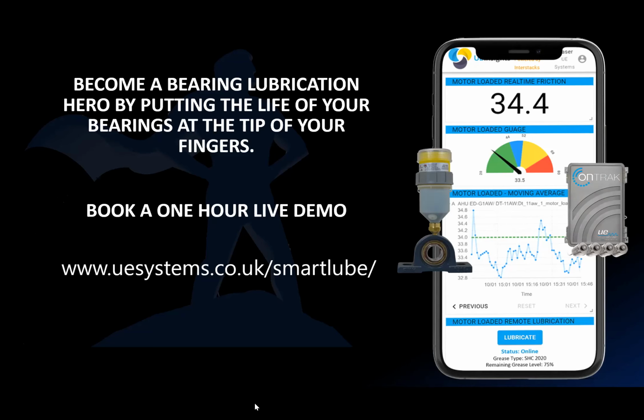Can this system be used to monitor friction on oil lubricated bearings? That's an interesting one. We can actually handle grease and oil. Specifically, if you get into journal or sleeve bearings, the technology we're measuring is friction and impacting, and typically you see those in later stage failures. So the standard with journal or sleeve bearings is a prox probe, because you're looking at distance. It's not designed to give you that early notification. You could use it, but it's not designed for that. But if it's an oil system, you could put it in for sure, and that would come down to specific applications we could talk more about.